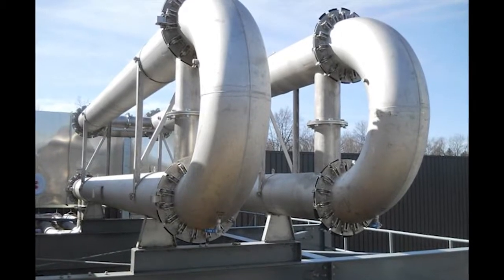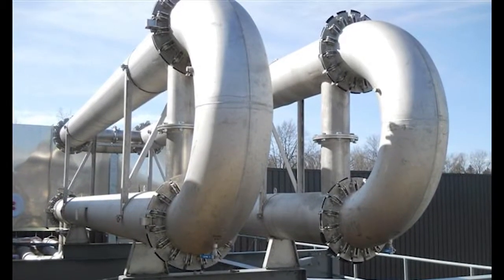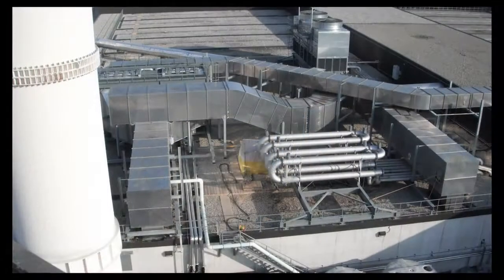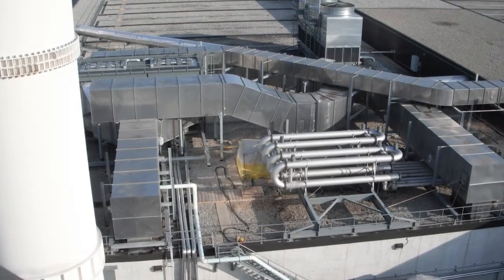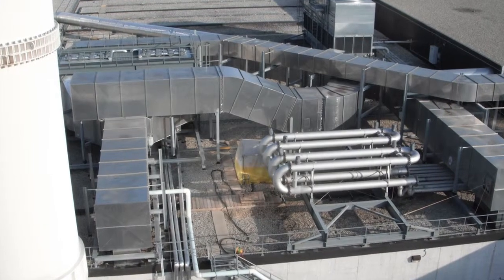After the ammonia scrubbers, the air travels through the cooling system, which is the first step of the wet bio scrubber. The air is first cooled and then proceeds into the bio scrubber where it is humidified. Natural organisms consume odorous compounds in the bio scrubber. The air is humidified to help encourage the biofilter life activity and it also has its own odor removal effect.